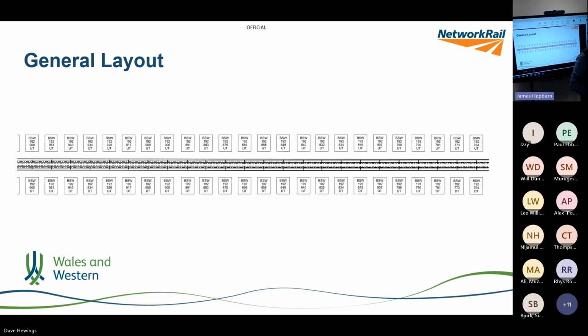So how do you apply that to Severn Tunnel? It's very boring, isn't it? Here's an extract of the overhead line layout diagram, which is usually full of exciting things like overlaps, anchor wires, midpoint anchors, and all sorts of tensioning devices. This just plods its way through the tunnel with very closely spaced structures. Everyone's got an identity, but they're effectively stovepipes - drop tubes from the roof of the tunnel - very closely spaced, 7-8 meters apart, not much different really to the dropper spacing on a normal catenary system. So very closely spaced, lots of structures - 1,400 in the whole tunnel, all drilled into the roof of the structure.